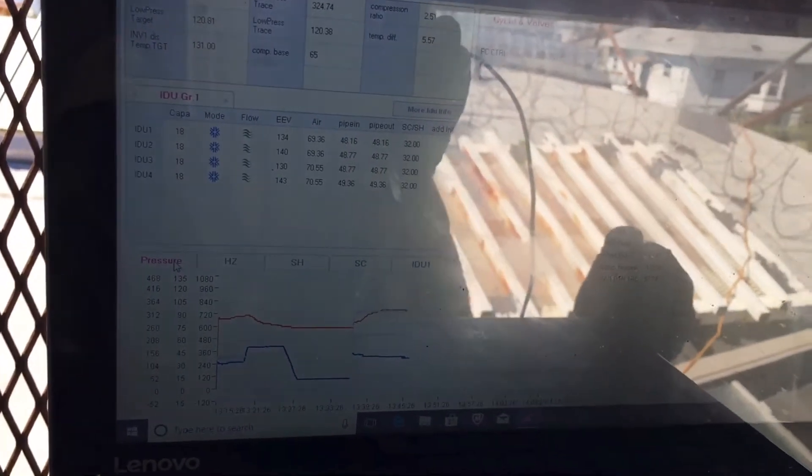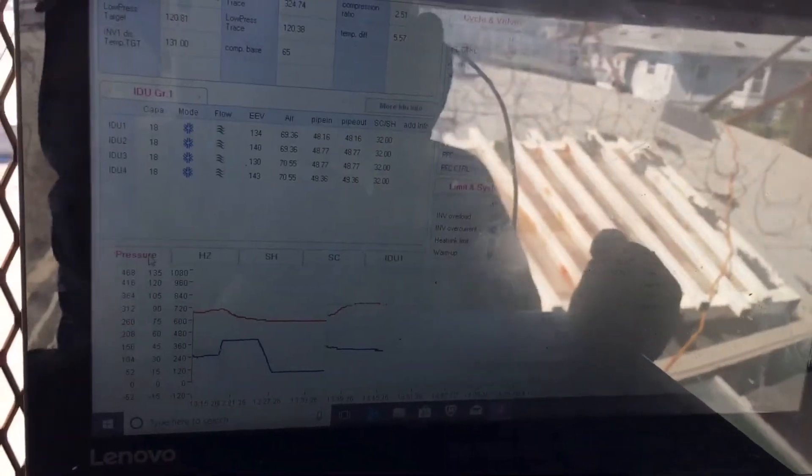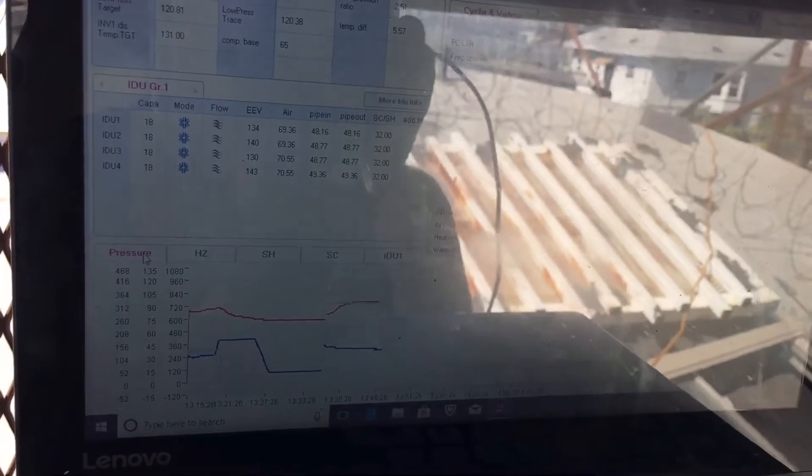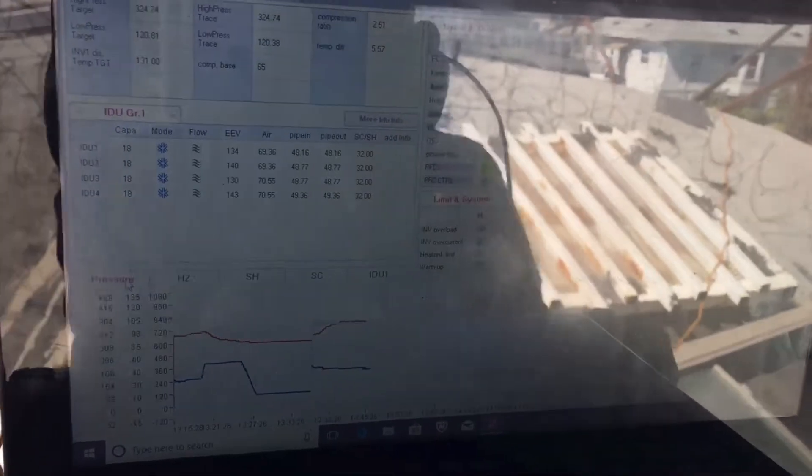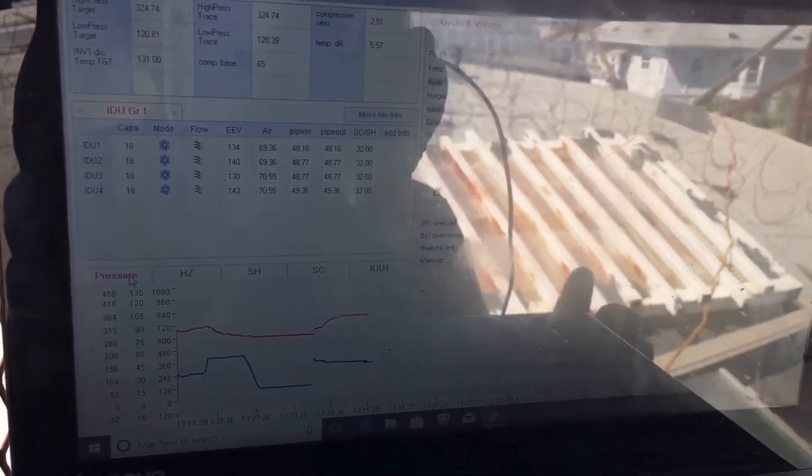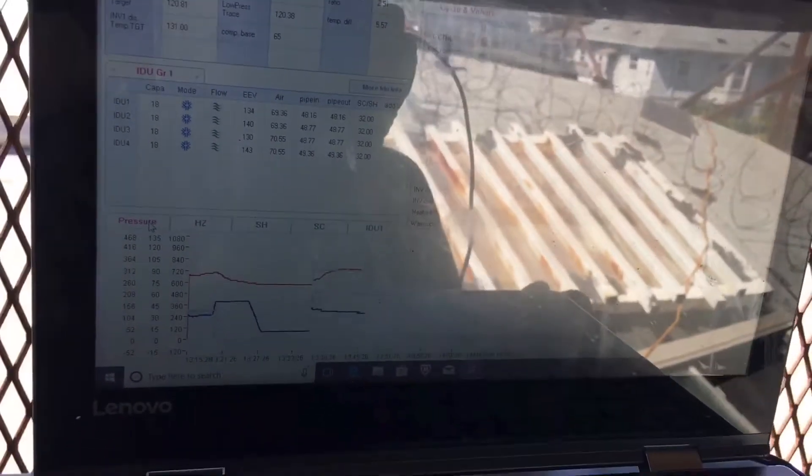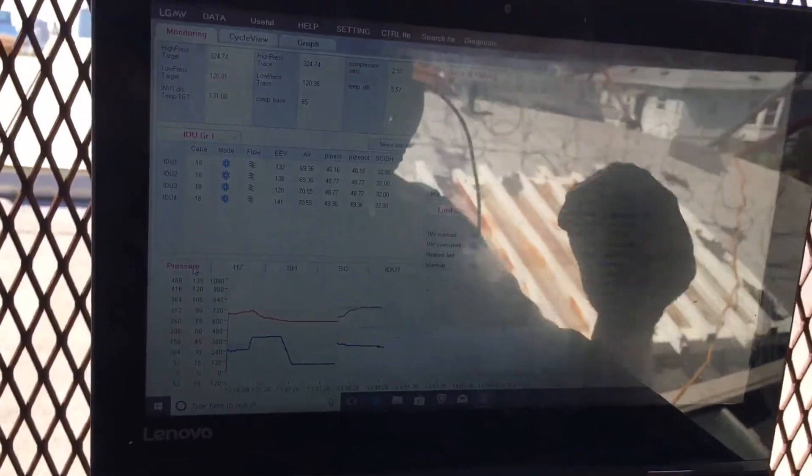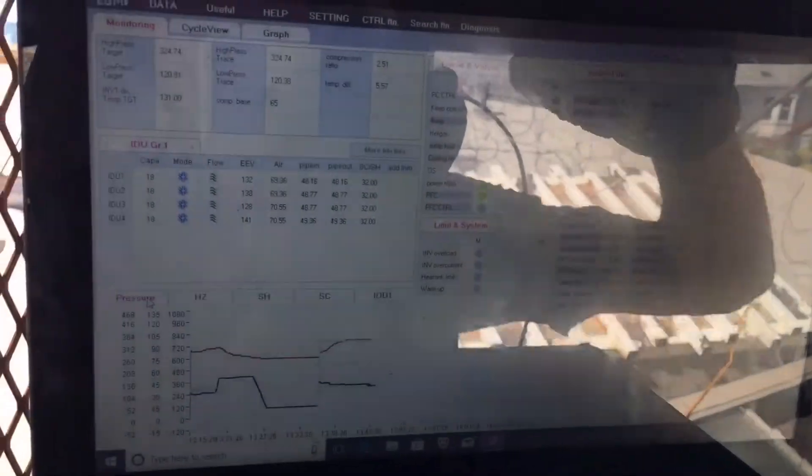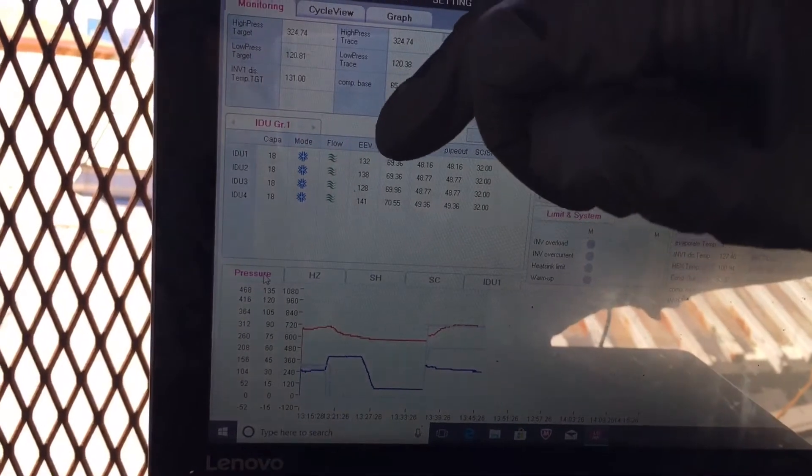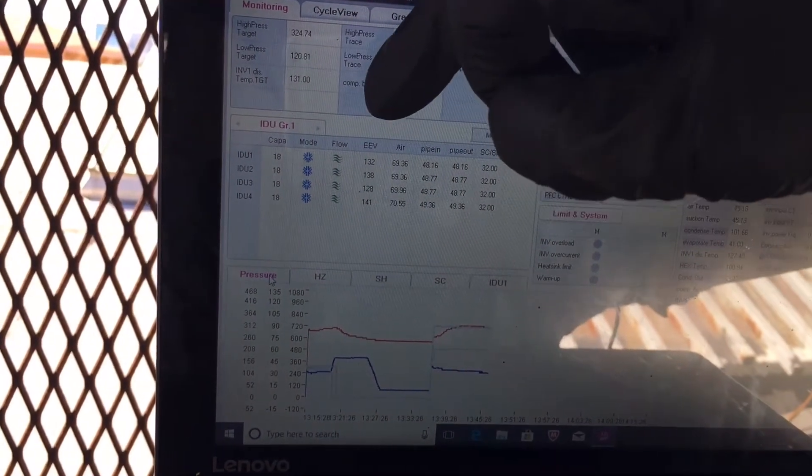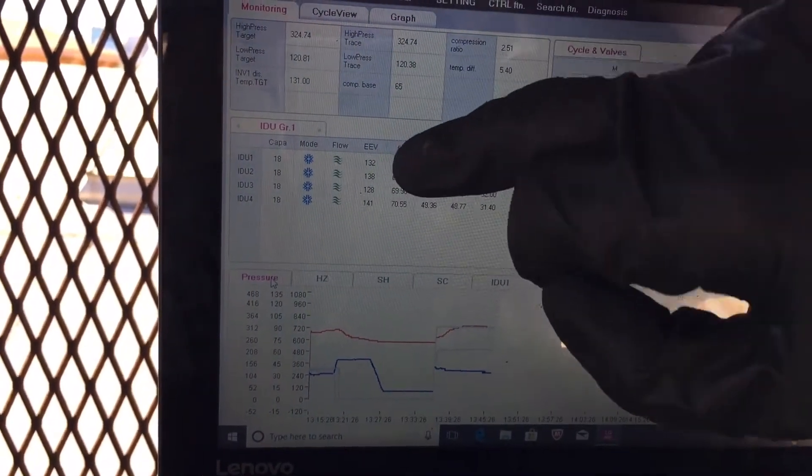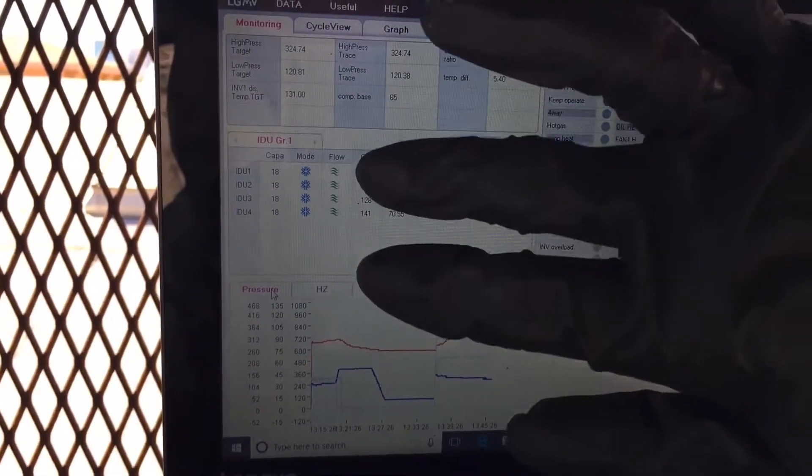I've come across so many of these systems overcharged several pounds or undercharged, all because somebody grabbed it with their hand and were trying to go beer can cold, or they were using their gauges and trying to go to a PT chart and the temperature of the day and some bullshit like that. You do not do these on these units at all.